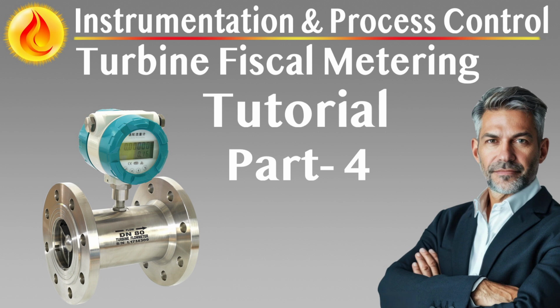Each microcomputer, stream, station, and prover must be equipped with self-diagnostics capable of detecting internal hardware faults, communication errors, and abnormal operating conditions. These diagnostics must generate alarms and provide detailed feedback to the station microcomputer, enabling prompt isolation and resolution of faults. If a stream microcomputer fails, the system must automatically deactivate the associated meter run and prevent the use of invalid data. If a data link failure is detected between system components, the fault must be clearly enunciated without affecting the standalone operation of individual devices.